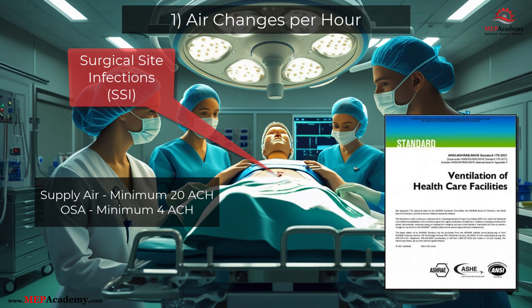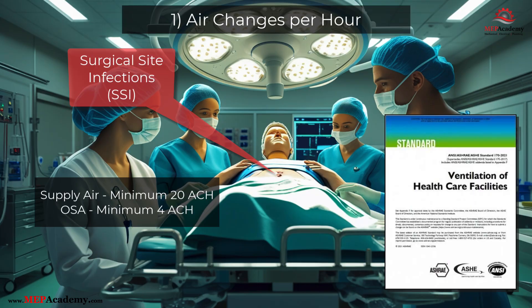The minimum of four air changes per hour from outdoor air is to dilute airborne contaminants like bacteria, viruses, and aerosols generated during surgery. This high ventilation rate, mandated by ASHRAE Standard 170-2021, ensures rapid removal of particles and maintains a clean environment, with HEPA filtration capturing 99.97% of particles greater than or equal to 0.3 microns.